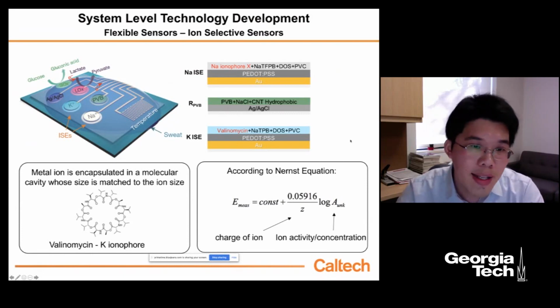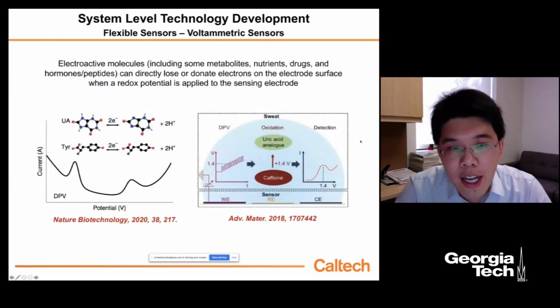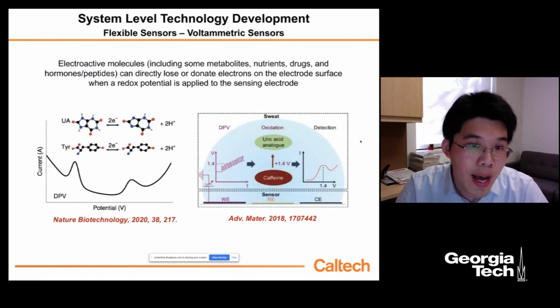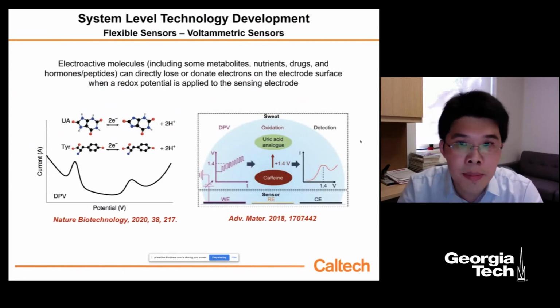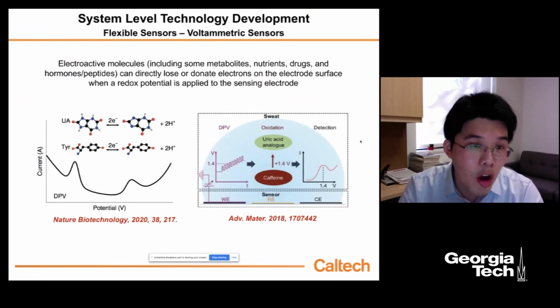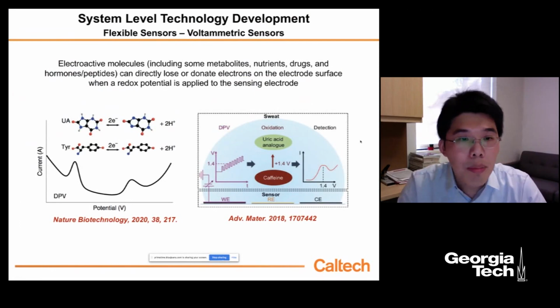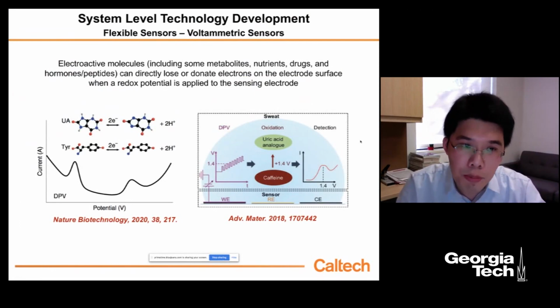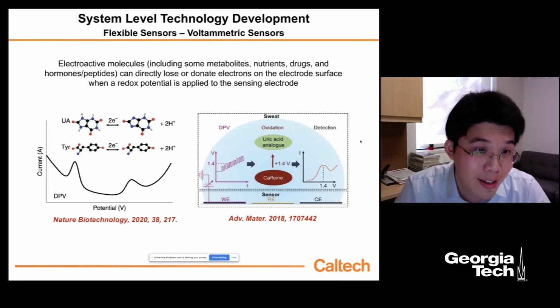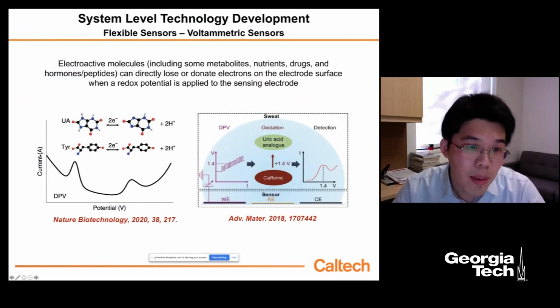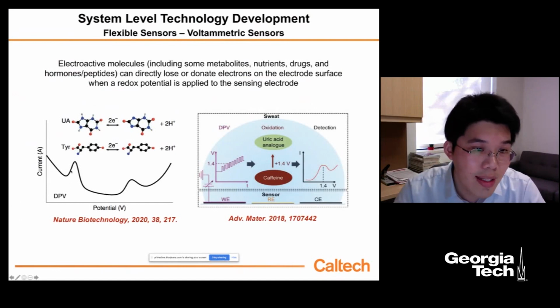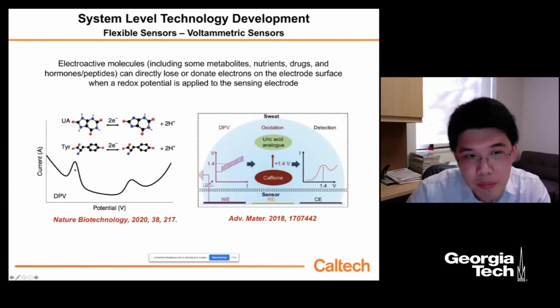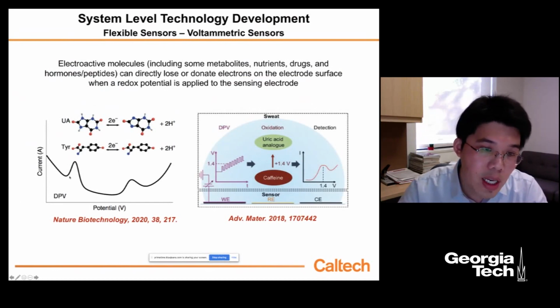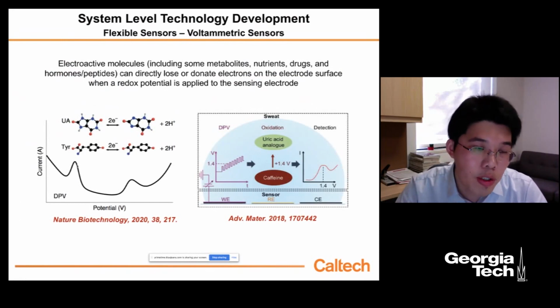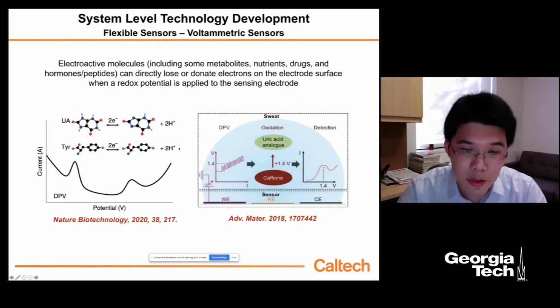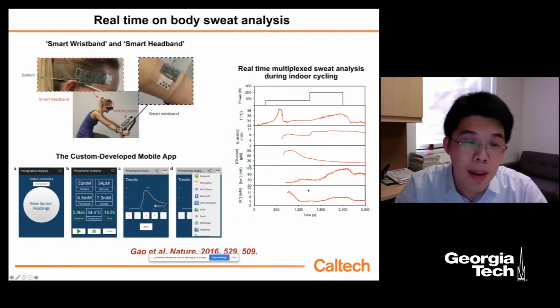In addition to enzymatic electrodes and ion-selective electrodes, we could also monitor targets through voltammetric sensors. Many electroactive molecules, like uric acid, some amino acids, vitamins, and drugs, can be oxidized on a given electrode at a certain voltage. So we can apply this voltage to measure the oxidation reaction, and the current amplitude is proportional to the target concentration. For example, to detect uric acid, we can apply differential pulse voltammetry. Uric acid will be oxidized at one given voltage. The first peak on the left picture is the uric acid peak. The peak height is proportional to the uric acid concentration, so we can convert back to the target concentration. These are the three main methods used for wearable electrochemical biosensing.